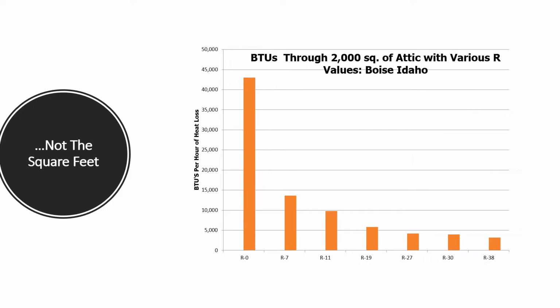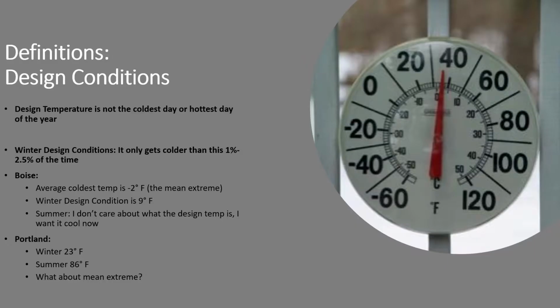This is another way of looking at the same information. This is BTUs through a 2,000 square foot attic with various R values. Again, we're in Boise. At R0, oh my gosh, 42,000. That's a gas furnace all by itself. By the time we get down to R7, we get a big jump down, and at R38, boy, we're much lower. This is not to say that high R values aren't important. Why not stop at R11? This is to say when it comes to sizing of equipment, the biggest differences come when you make a low R value higher. Let's get some definitions out of the way.